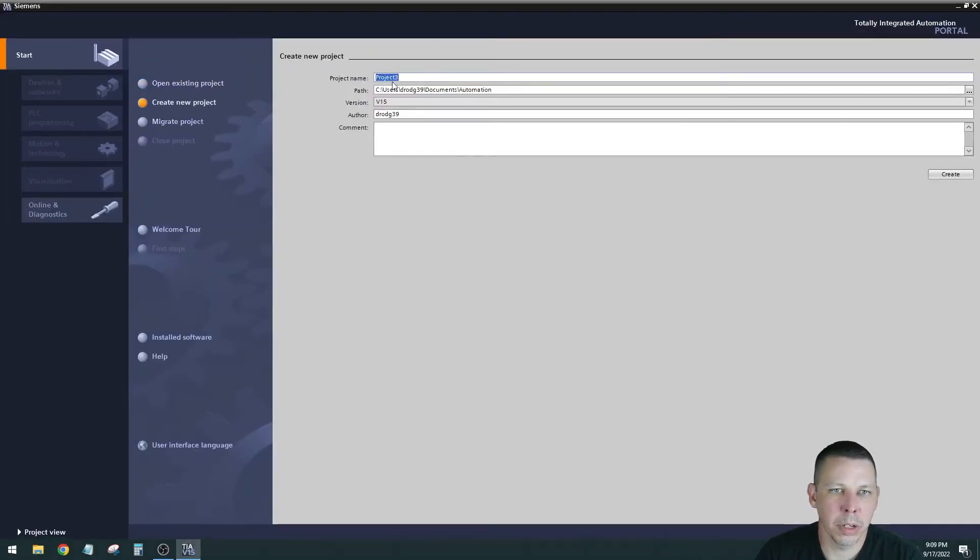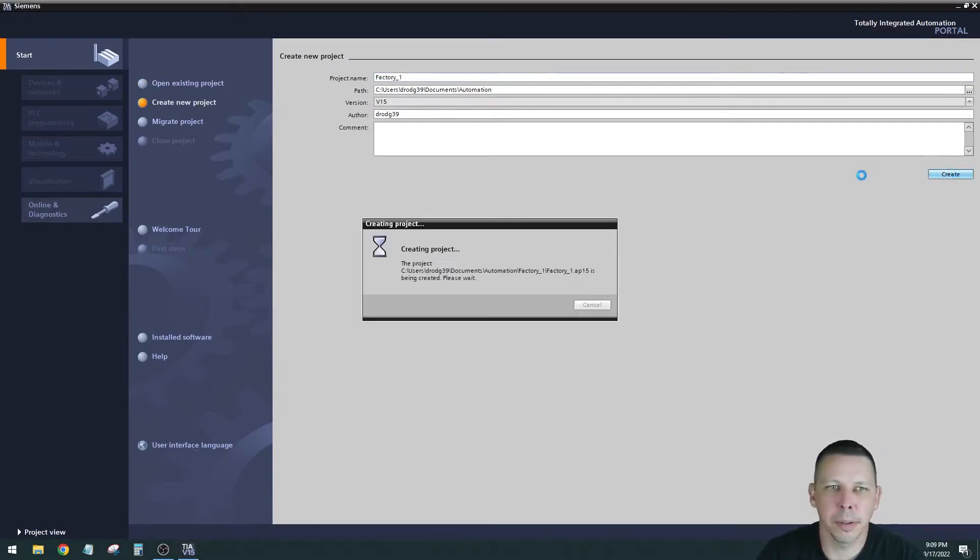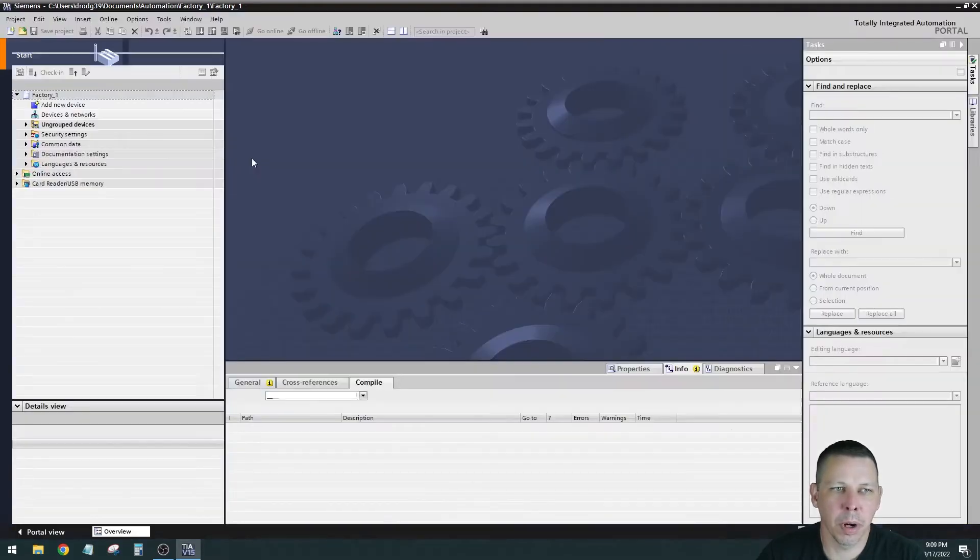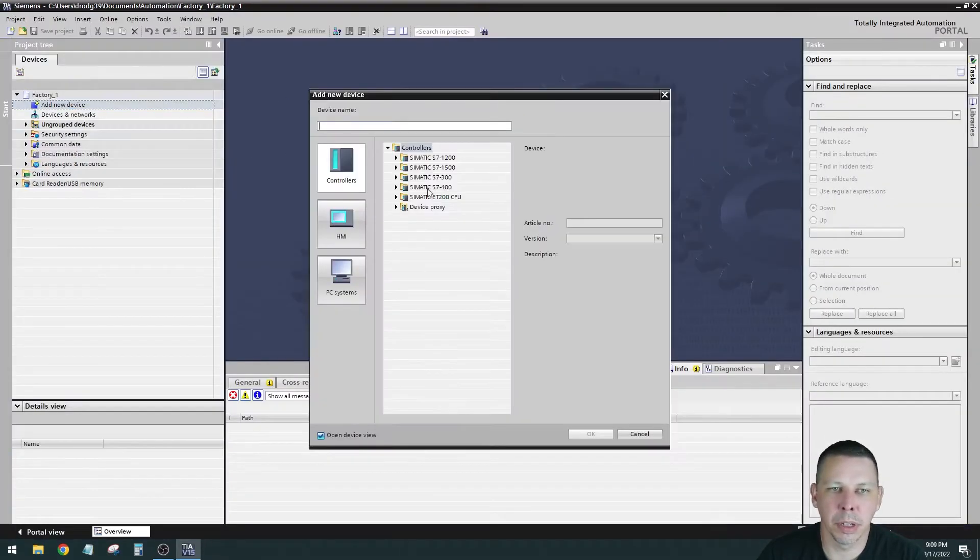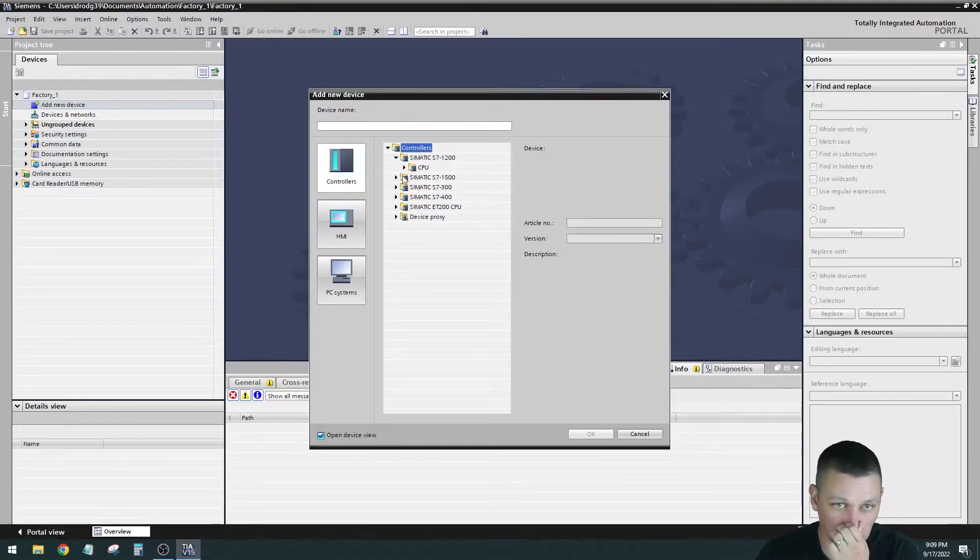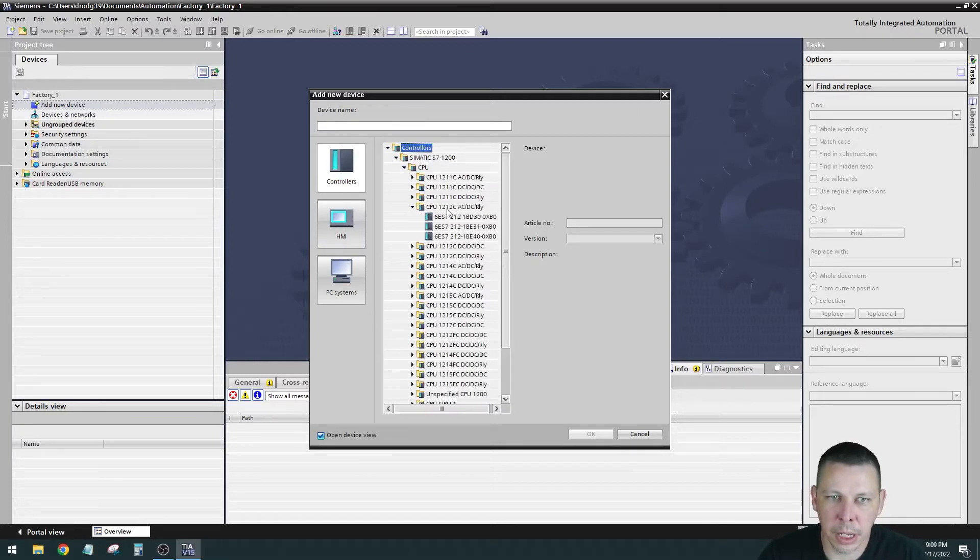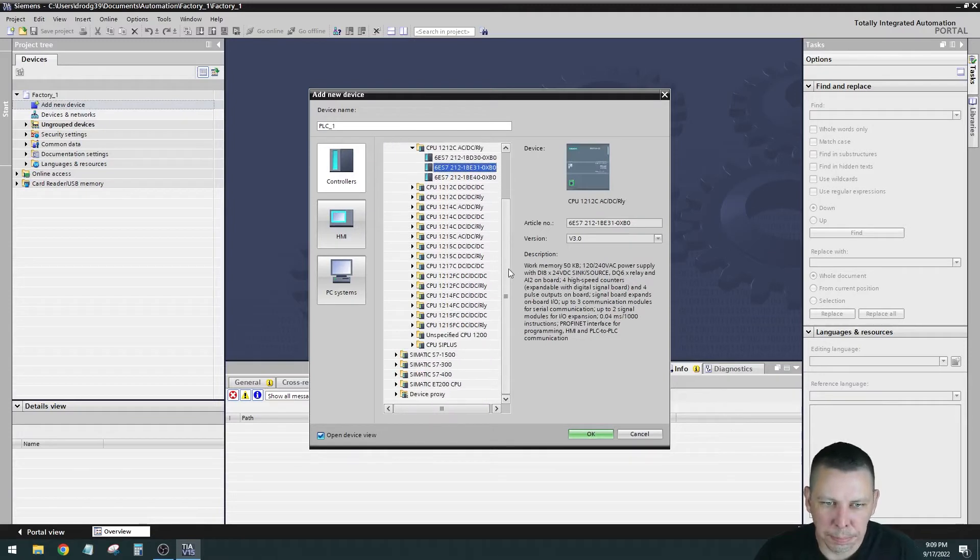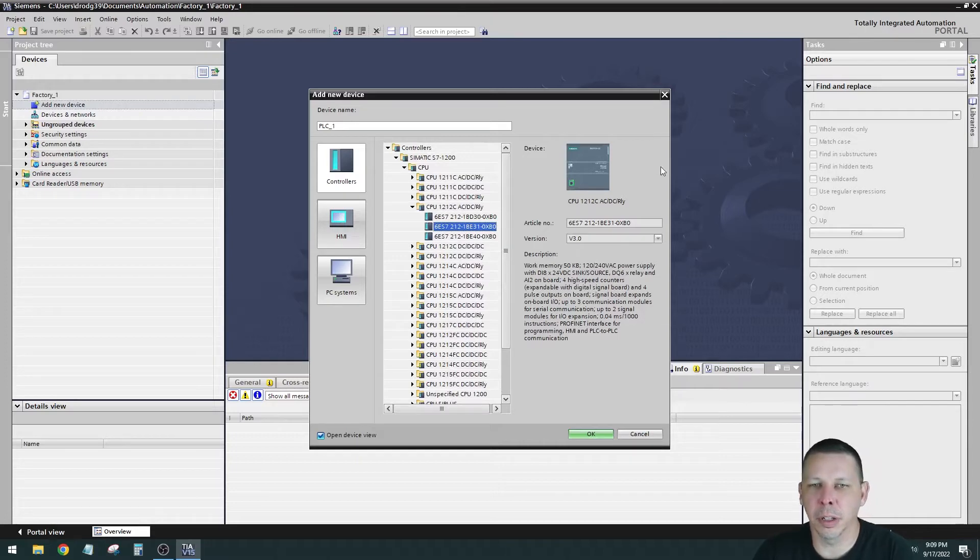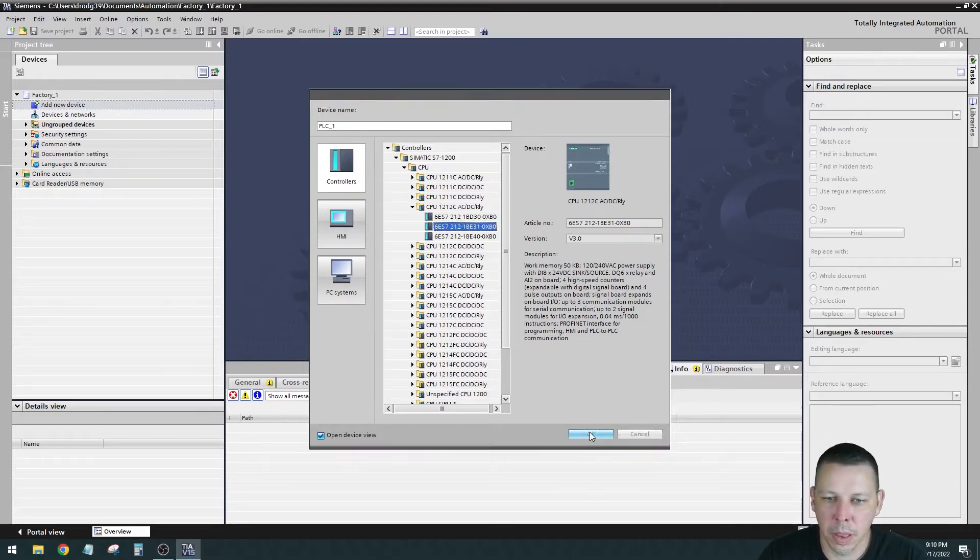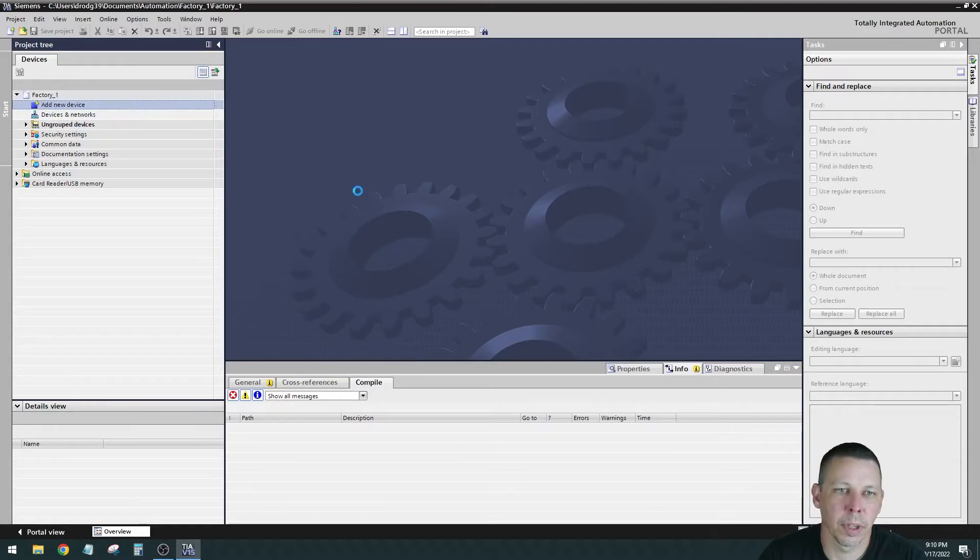Create a new project. I'm just going to call it Factory 1. Create. Takes a minute to create. Then if you remember, our next step will be going to project view. Down here we're going to add our processor. Add new device. It's going to be a double click. We're in controllers, S7-1200. I have a 1212C AC-DC relay and I have the middle firmware. There's also a way if you don't know what you have or if it's in an enclosure where you can automatically detect processor, but we know what we have.